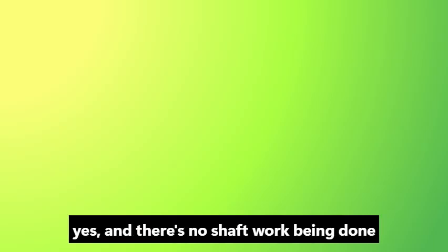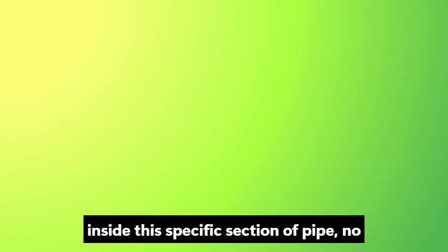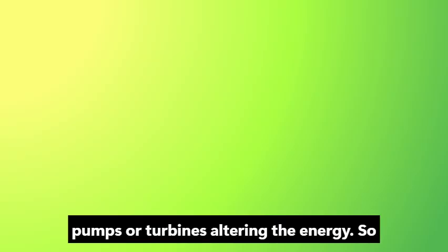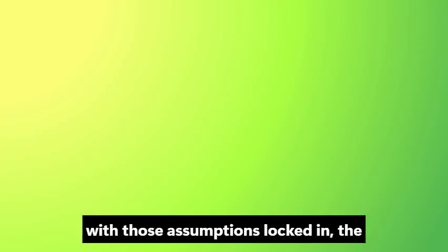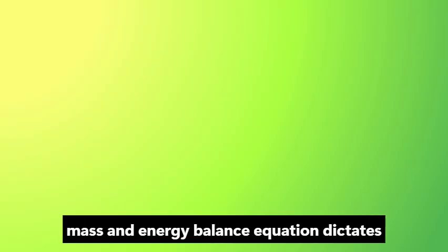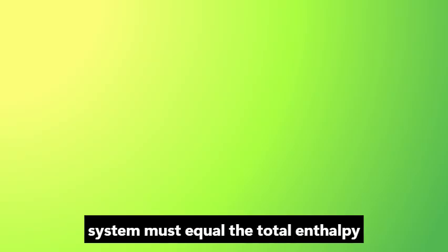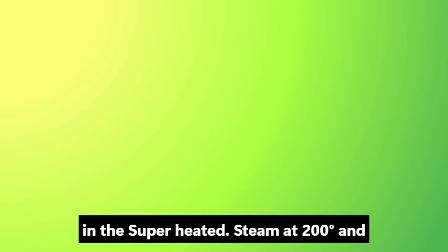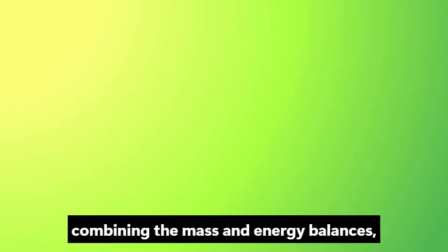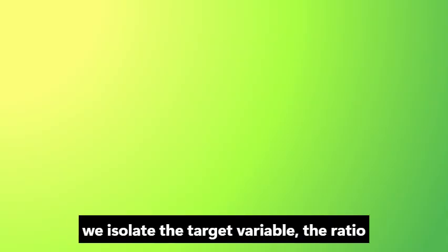Yes, and there's no shaft work being done inside this specific section of pipe, no pumps or turbines altering the energy. So with those assumptions locked in, the mass and energy balance equation dictates that the total enthalpy entering the system must equal the total enthalpy leaving it. We have two streams flowing in, the superheated steam at 200 degrees and the subcooled liquid water at 50 degrees. And one single stream flowing out, the dry, saturated steam at 6 bar. Exactly. So by combining the mass and energy balances, we isolate the target variable, the ratio of the injected water mass to the incoming steam mass.